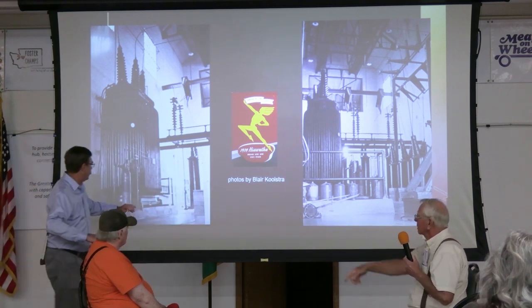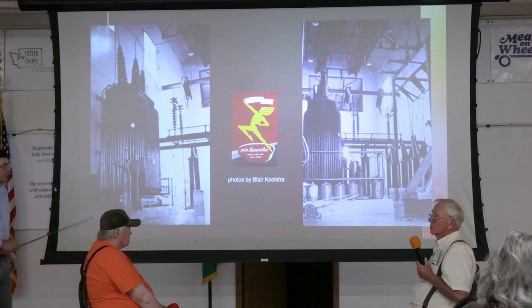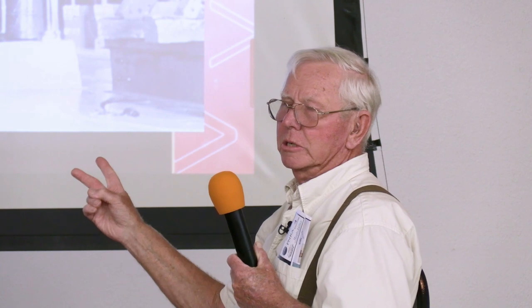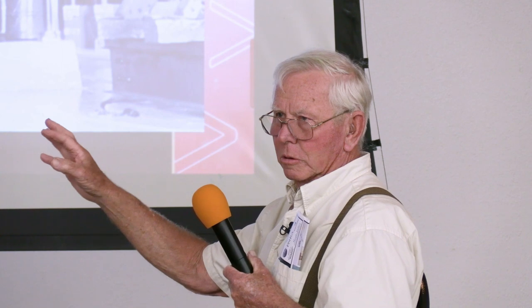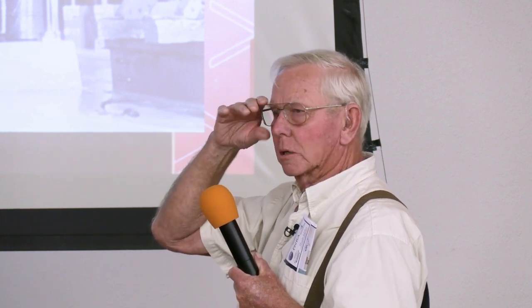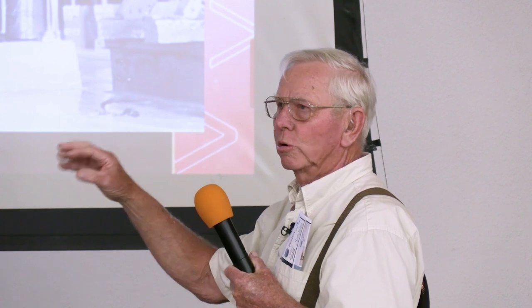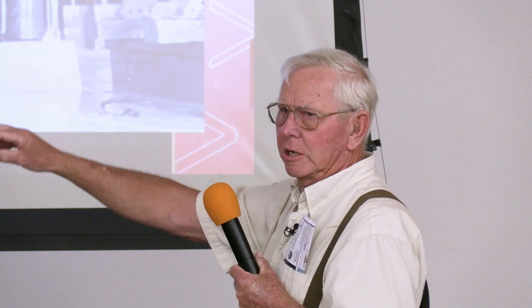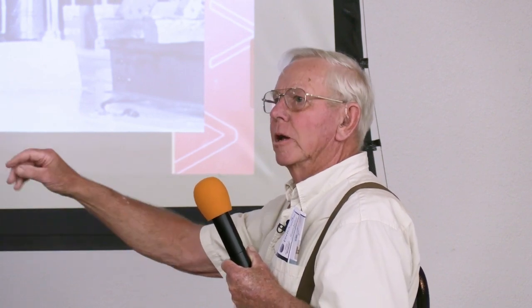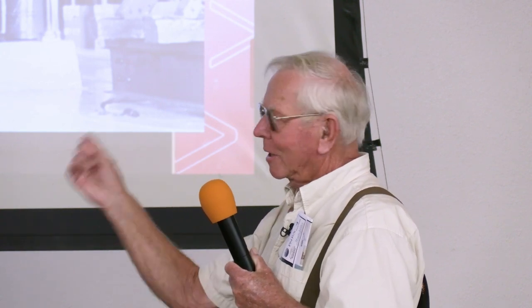And down underneath there is a basement. There are two spaces in this case, since this was a 2 MG set substation. If it had been 3 MG sets, then you'd have three of those spaces. Down below there were, I think, like 500 gallon holding tanks. When you drained the oil out of the transformer, you drained it into that holding tank, and that's what you pumped out through this press filter, round and round and round.